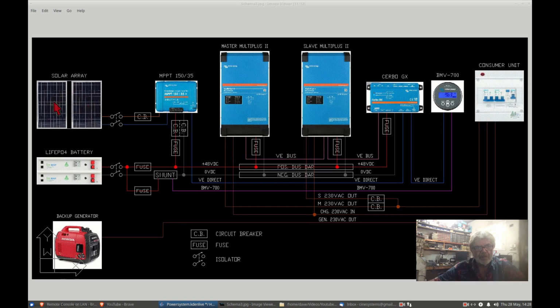So when we go to the solar array, I have a 9-panel system on this PV charger. There are 3 strings of 3 panels in parallel. That gives it about 110 volts open circuit, or about 80 to 90 volts maximum power. There's a double pole isolator on each string, a separate circuit breaker for each string, so 3 circuit breakers, and then to the input of the PV charger, which is a Victron BlueSolar MPPT 150/35. So it's 150 volts input at 35 amps output. So out of the MPPT we have a double pole circuit breaker, inline fuse in the positive line, and then we go to the bus bars, pos and neg.